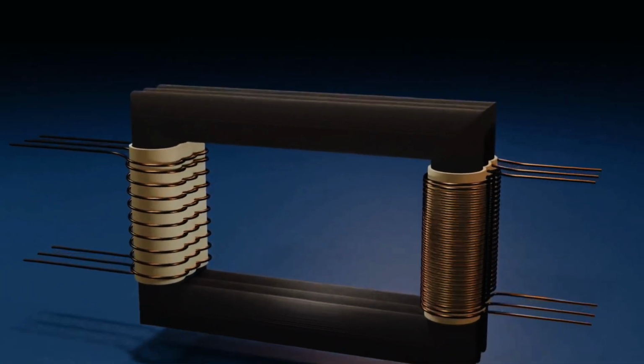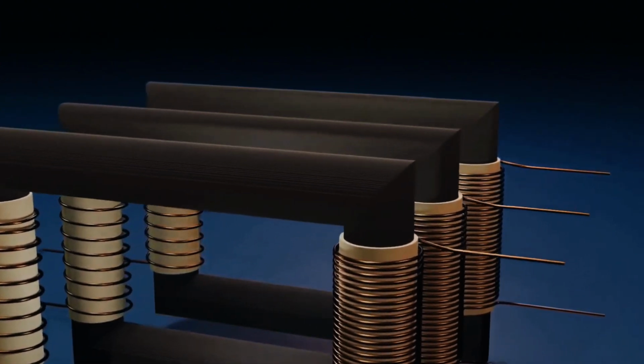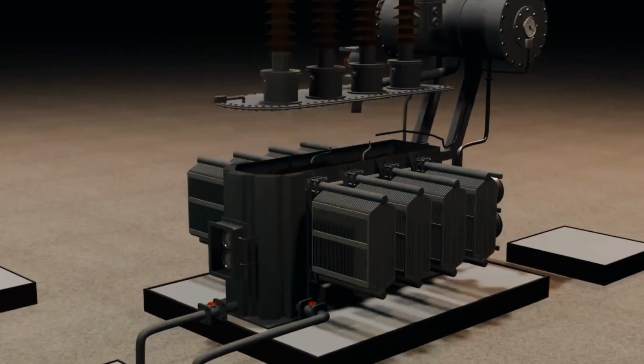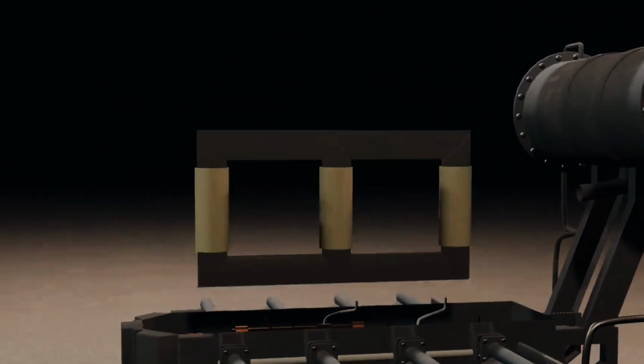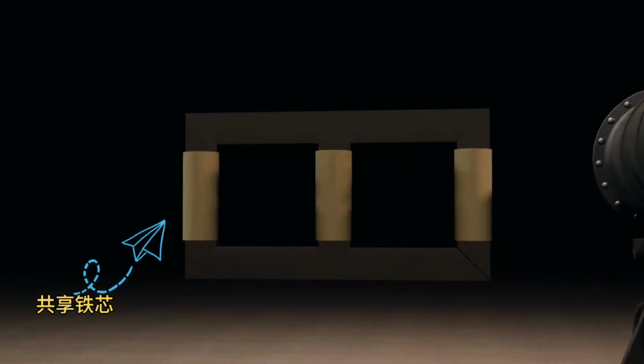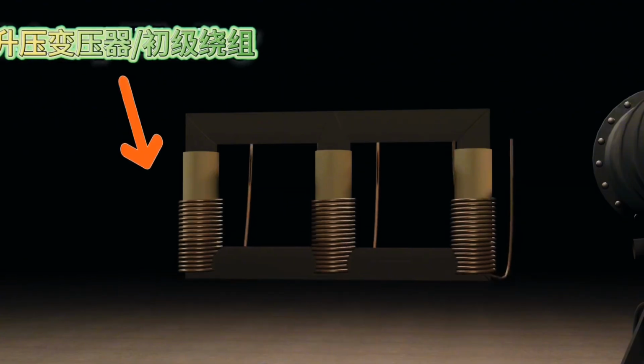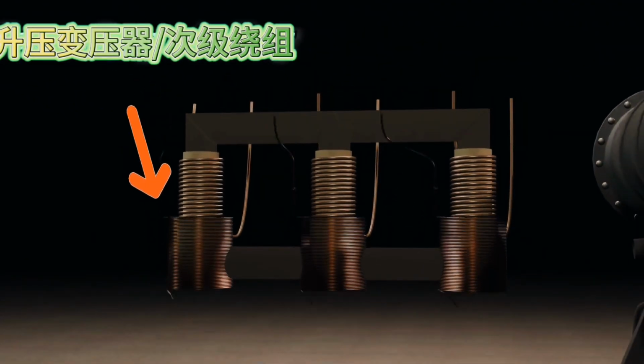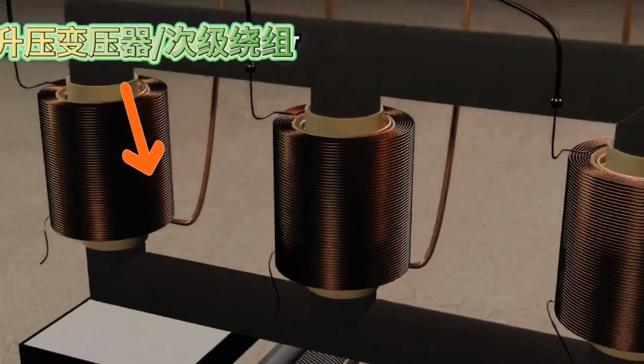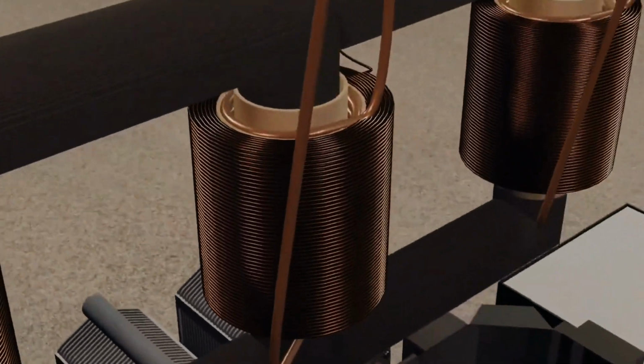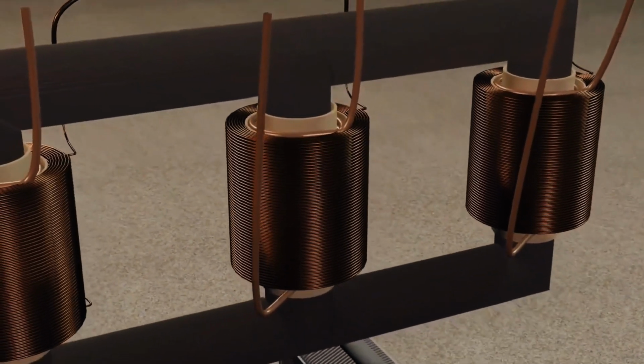A three-phase transformer is one of the most commonly used types of transformers. It has three pairs of windings inside, but in actual transformers, its three pairs of windings share a single large core. In this setup, the coils are usually arranged concentrically, with the lower voltage coil on the inside and the higher voltage coil on the outside. Each set of coils is insulated from each other. Power transmission is completed only during the magnetic induction process.